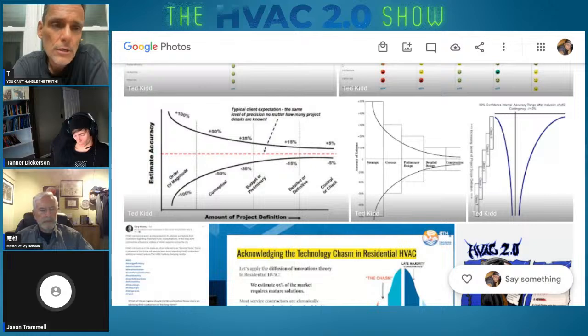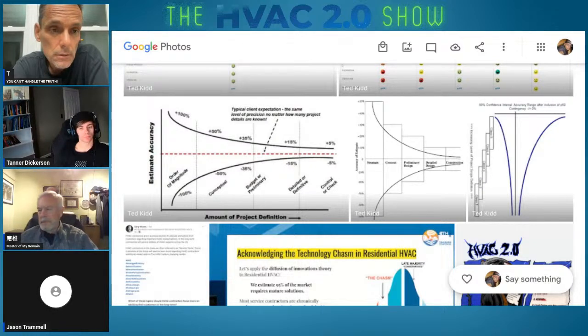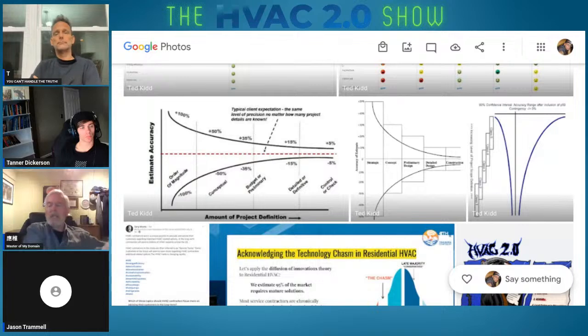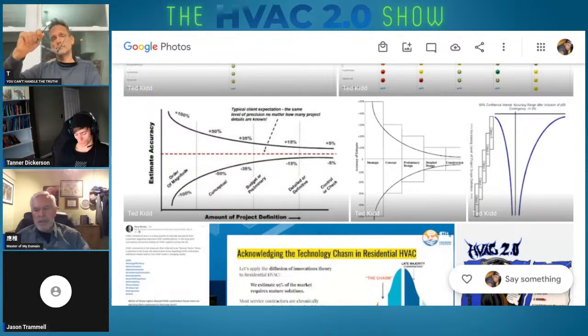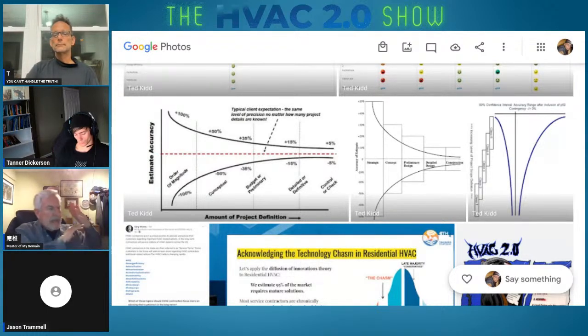You just said 99% of contractors aren't commissioning. That's Jason's point, and I was called in on something similar myself. A friend had a separate building erected on their property, and the builder used his own HVAC contractor. The owners had the contractor back each year and asked if there was any way to make the basement not so cold - they had a small apartment down there and other space upstairs. He said, 'Nope, can't do anything about it.' So when they had me go over, the first thing I looked at was airflow.